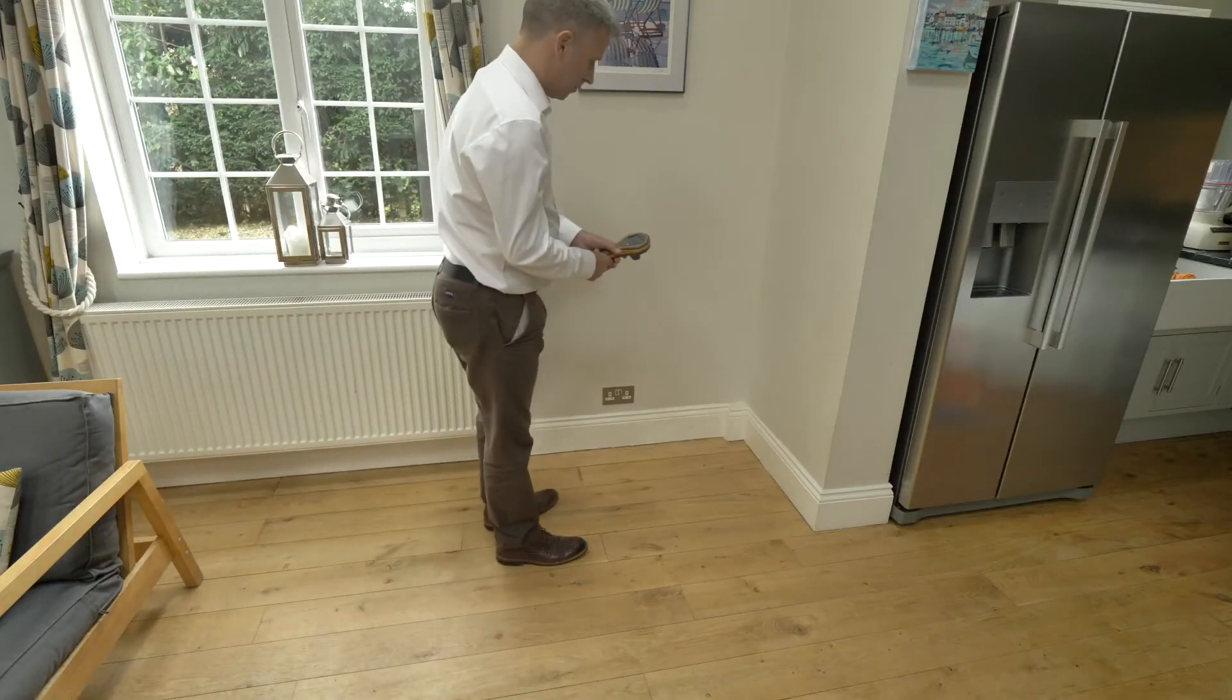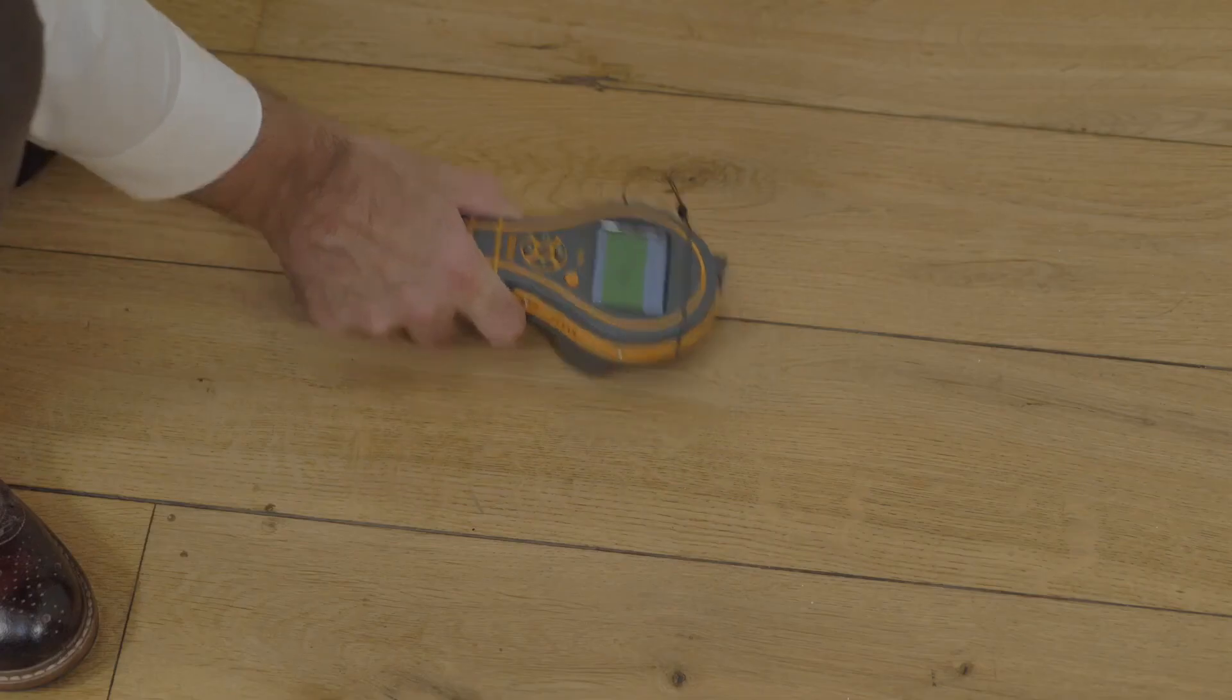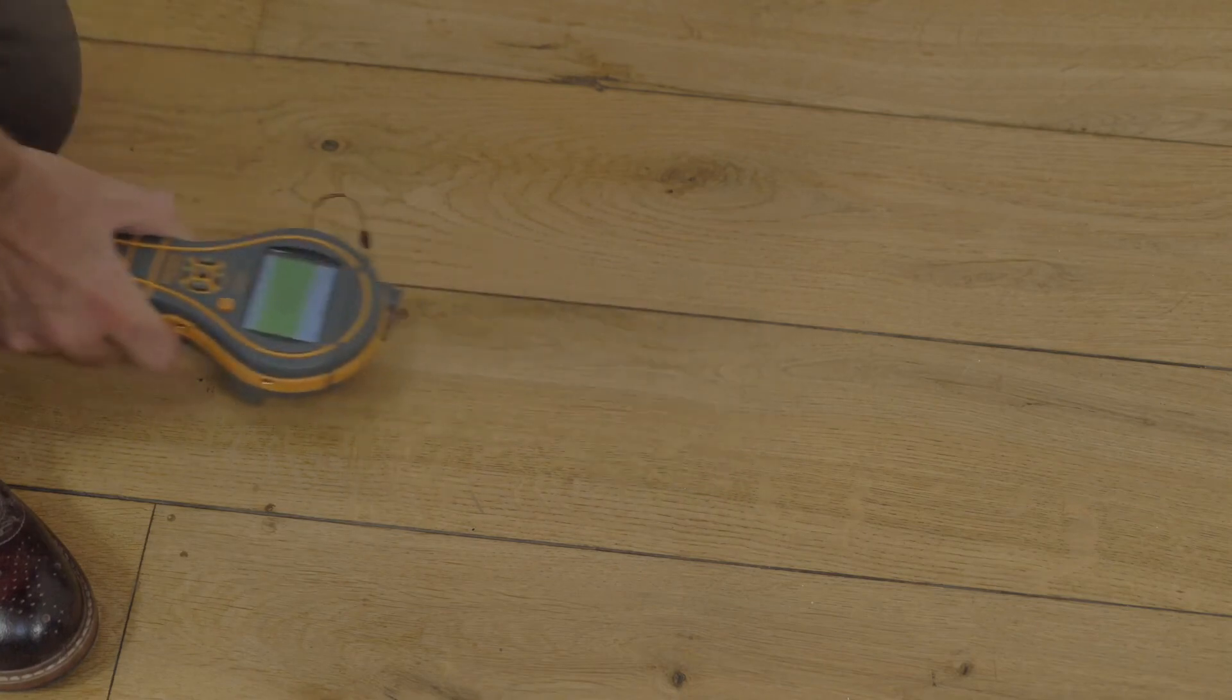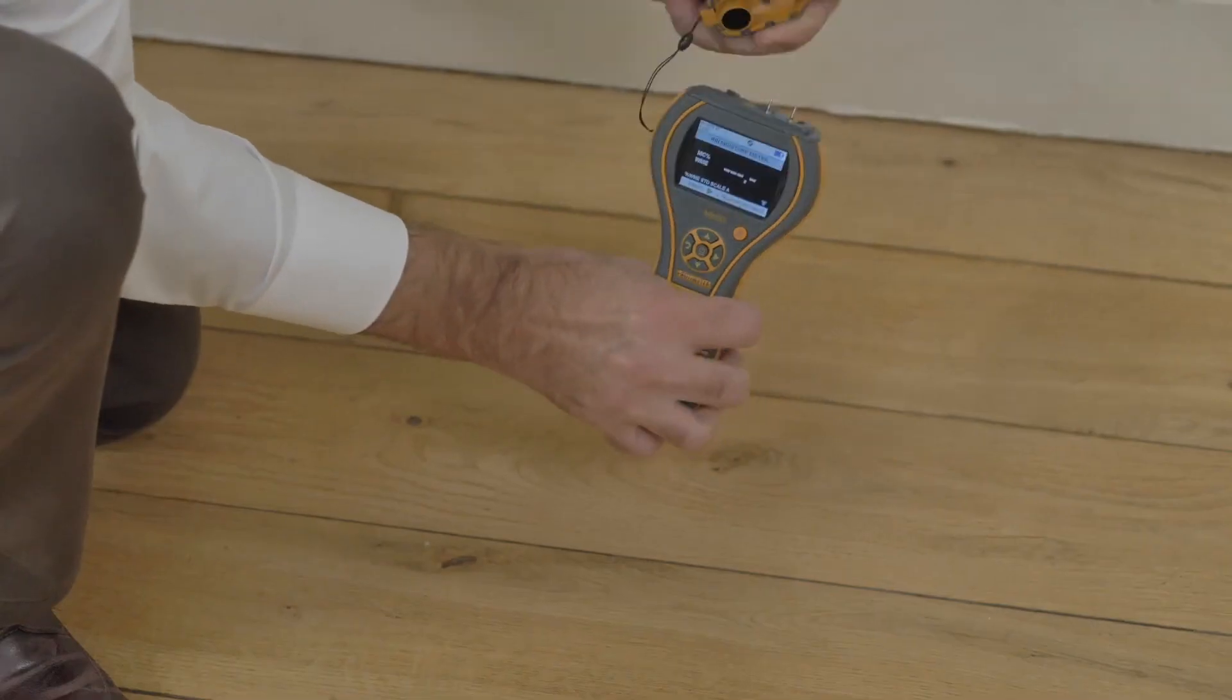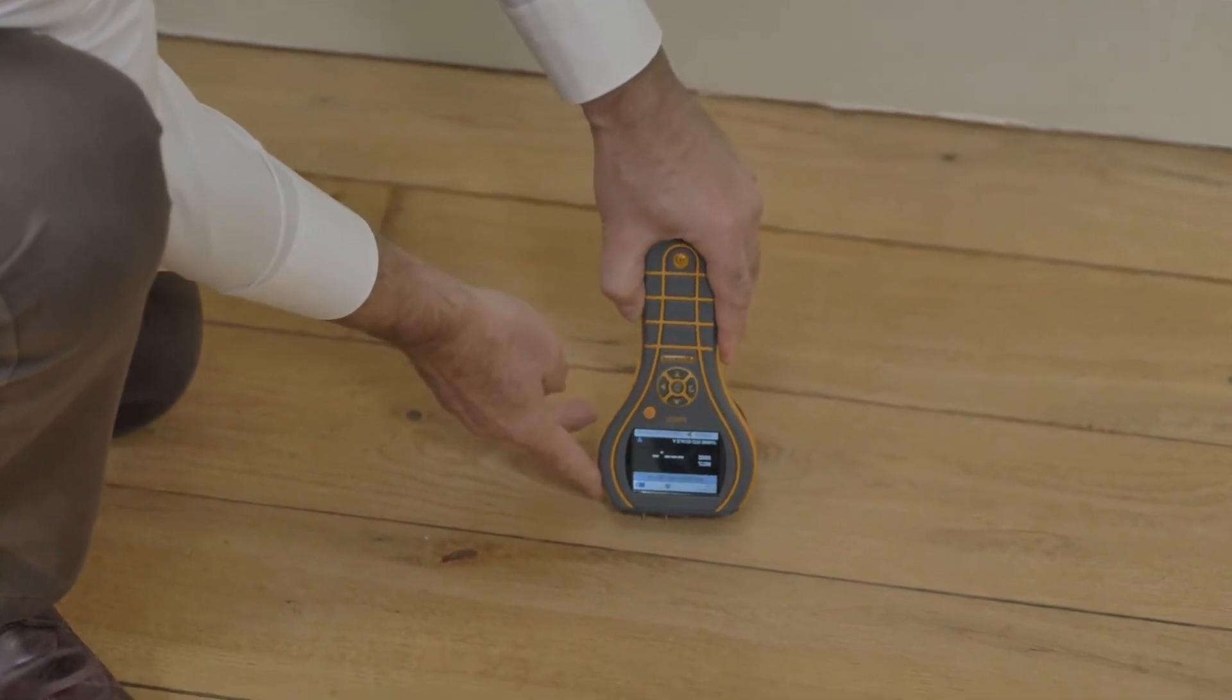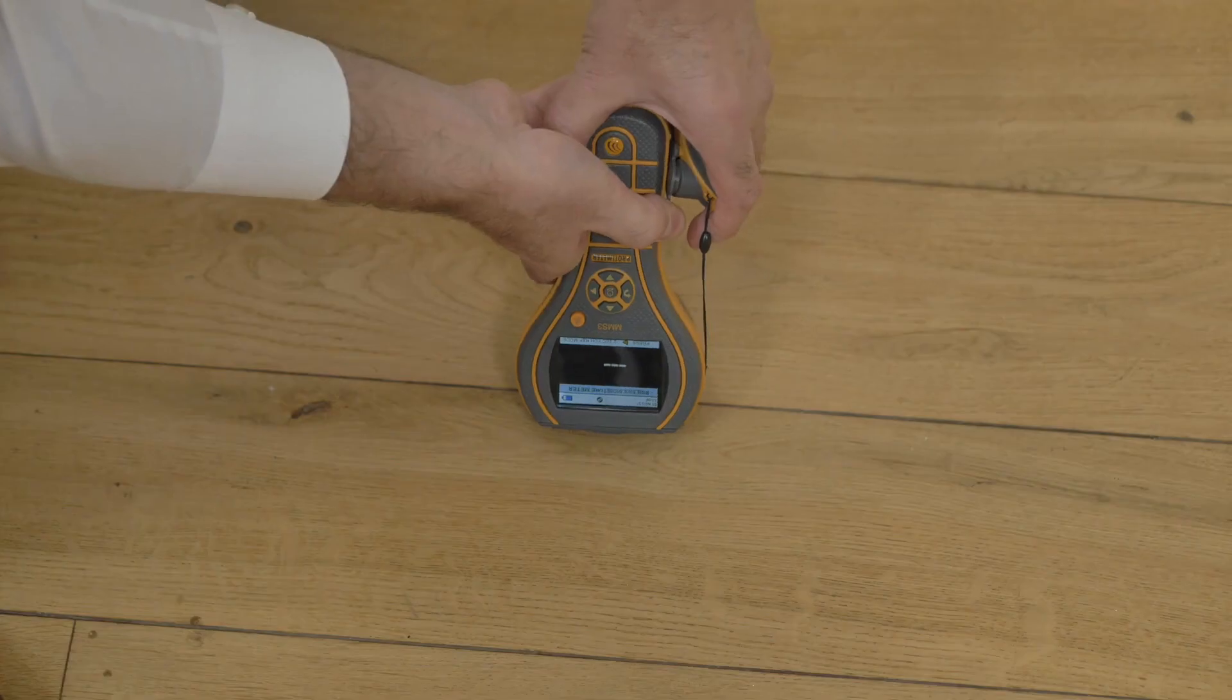Now we're going to look at the MMS3 in a wood floor situation. You can use the non-invasive to quickly assess areas of potential moisture. And then we can also use the pins in the surface of the material to see whether there's any moisture there. In this case, we can see no excessive moisture is present.